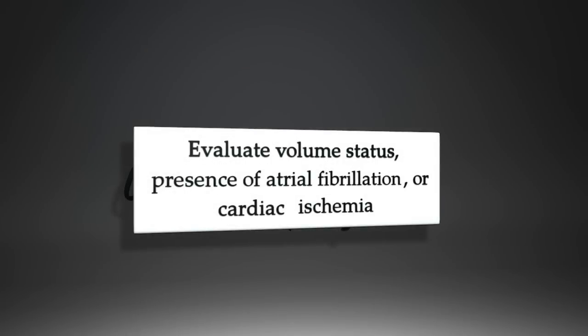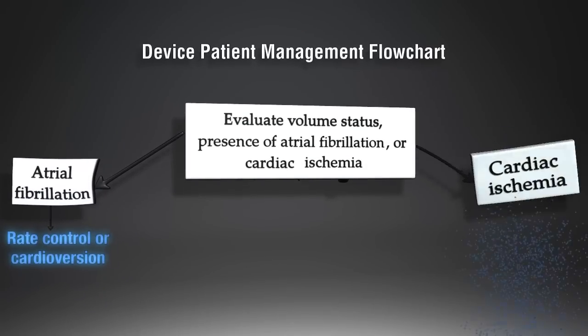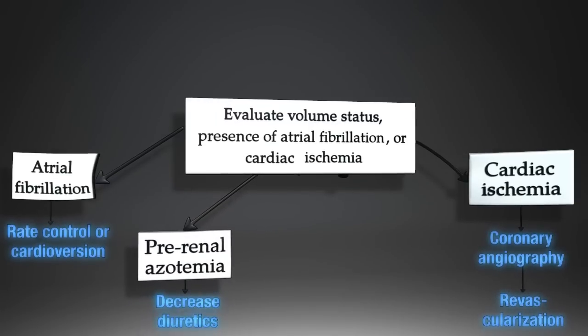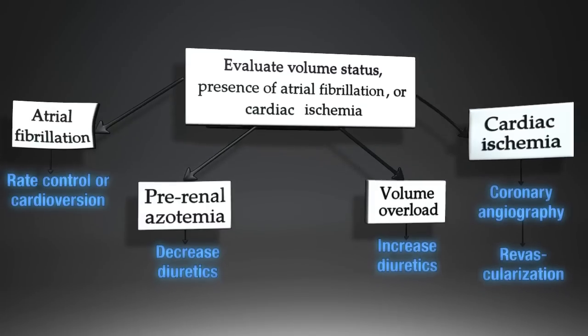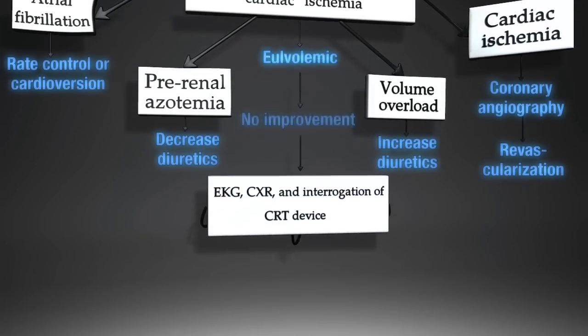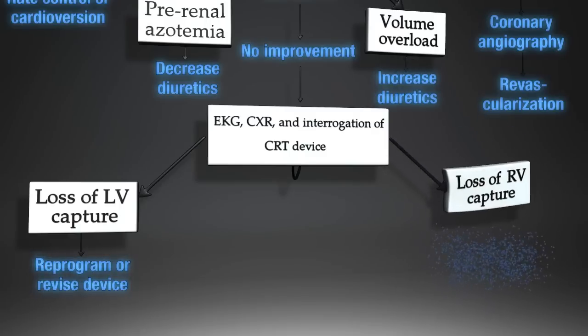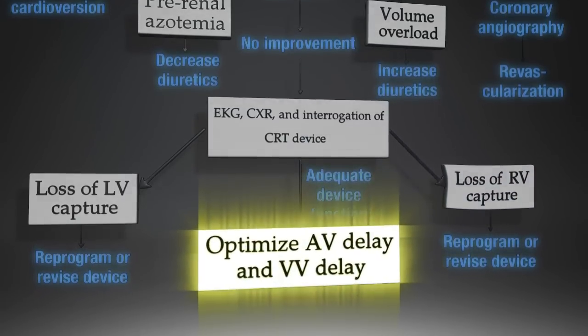Dr. Juan Aranda presented this flowchart for the management of non-responders during the ISHNE Worldwide Internet Symposium on Heart Failure in April 2006. Assuming no lack of RV or LV capture and proper device function, optimization of AV, PV, and VV delays is your first line of defense against the management of non-responders.